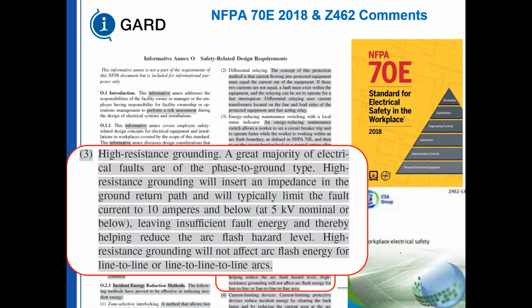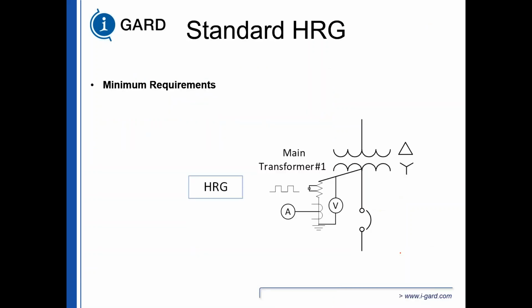Again, high resistance grounding. A great majority of electrical faults begin as the phase to ground type. When high resistance grounding is employed, you insert an impedance, and if you limit that fault current to 10 amps or less for systems 5 kV and below, it leaves insufficient energy for the fault to propagate to a phase-to-phase or three-phase fault, and thereby becomes an arc flash mitigation technique.